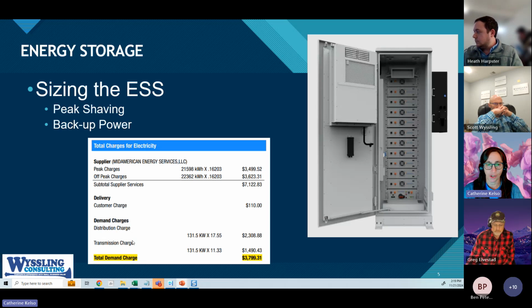It's called a demand charge. These demand charges are per kilowatt, not kilowatt hours, so that's how you can identify them. And you can see here on this bill that the demand charges are pretty hefty. They're $3,700 on this particular bill. And if you're sizing a battery system to deal with this, you have to look at the total amount of demand.